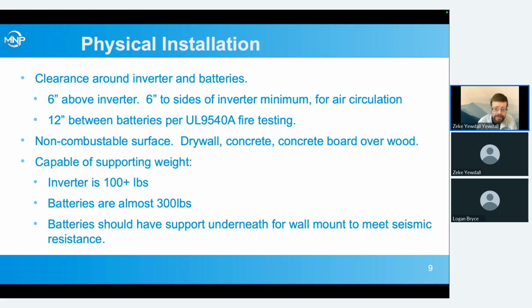We want it to be mounted on a non-combustible surface: drywall, concrete, or a layer of concrete board or tile backer over wood qualifies there. And obviously it has to be able to support the weight of the equipment. The inverter's a little over 100 pounds, the batteries are almost 300 pounds. You need a nice sturdy wall, and just some drywall anchors isn't going to cut it. Mounting to 2x4s or 2x6s in the wall, probably good.